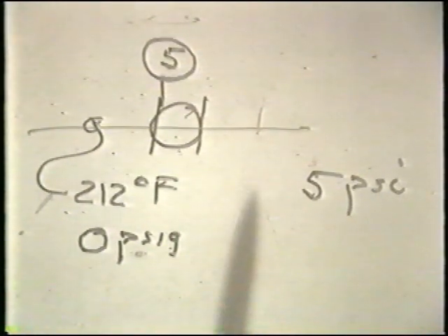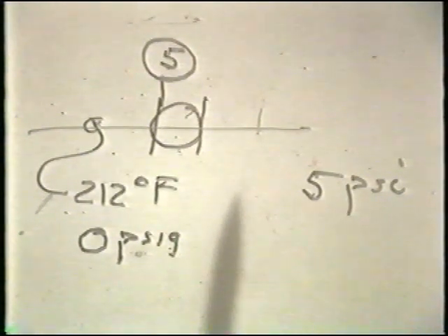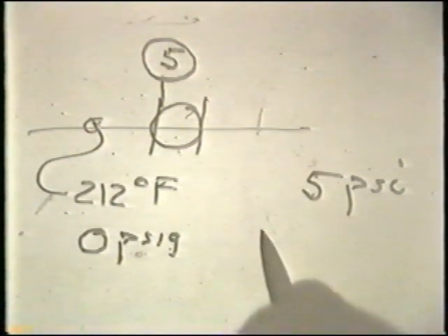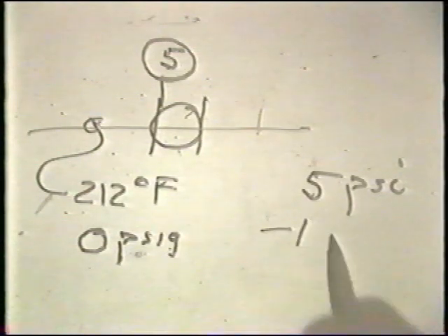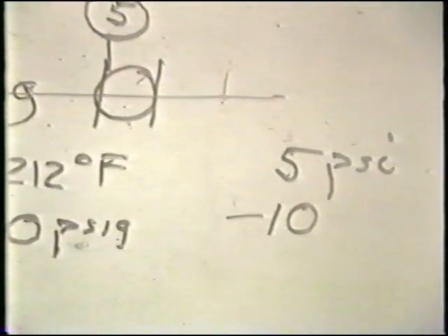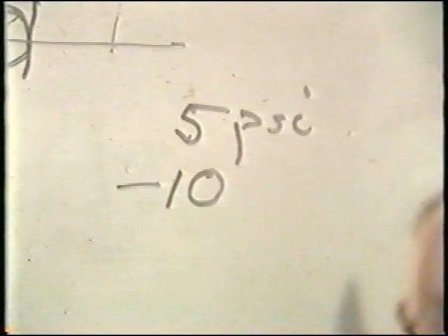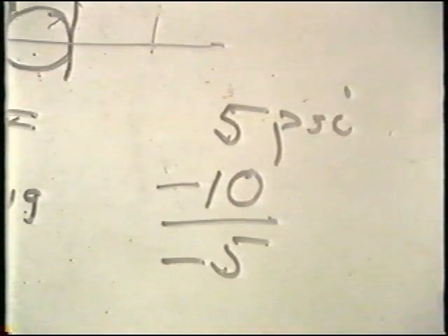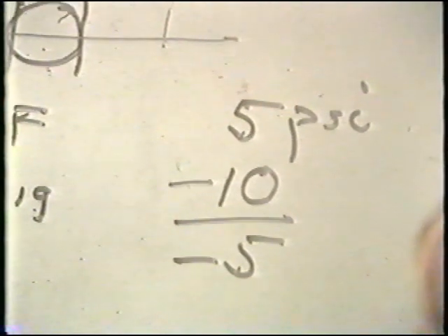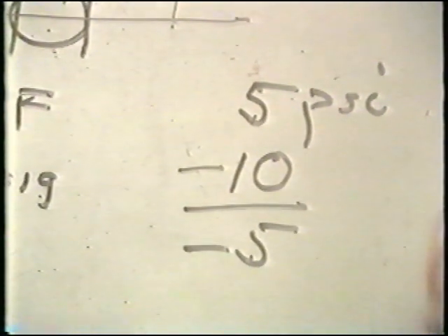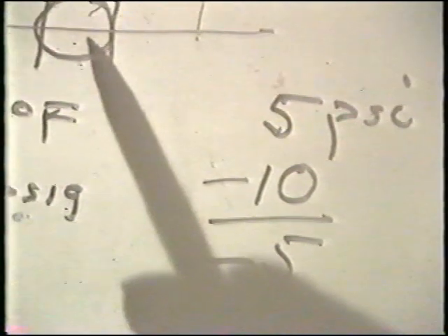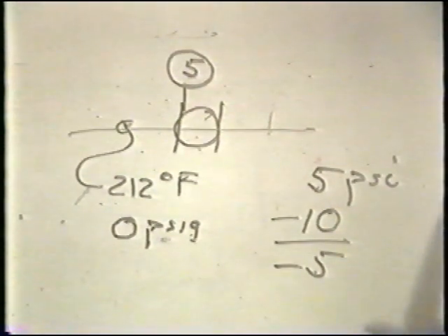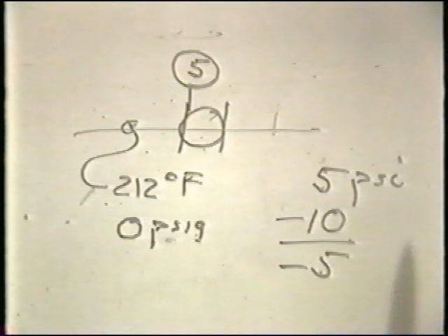Supposing now, however, we have selected a small pump, and that small pump has a pressure drop, required NPSH, of 10 psi. This would then mean that we are below the flash point of the liquid being pumped. The liquid would flash, cavitate, and we would have great troubles in terms of operation of that pump.